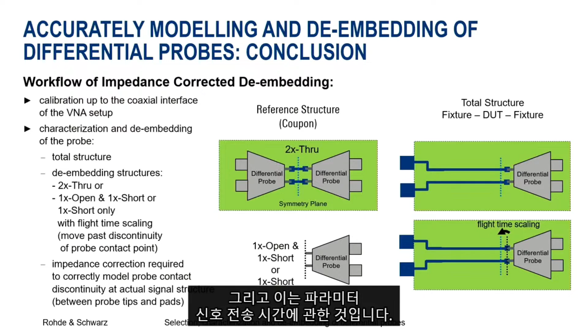And the other alternative is to use a 1x open and a 1x short. With the 1x open, you would leave the probe pins open. And with the 1x short, you would short the probe tips. With this, you are getting a reference plane right at the probe tips. And as we discussed earlier, you need to shift this reference plane from the probe tips a little bit into the structure. And this is what this parameter, flight time scaling, is about.